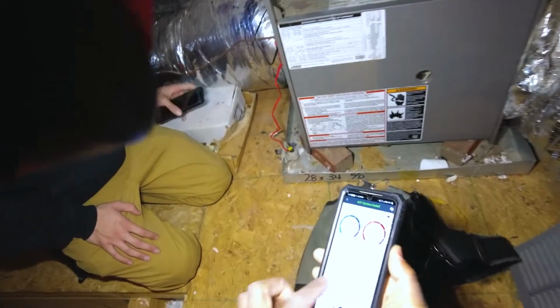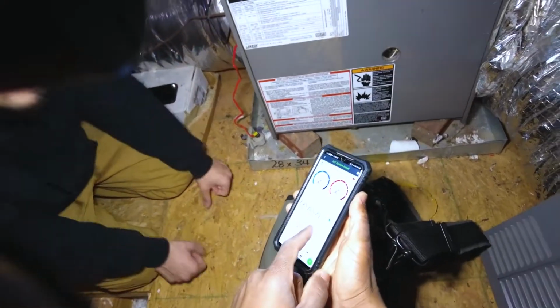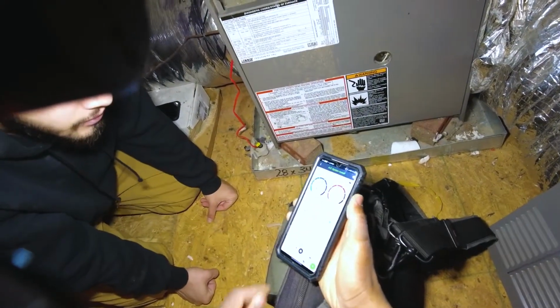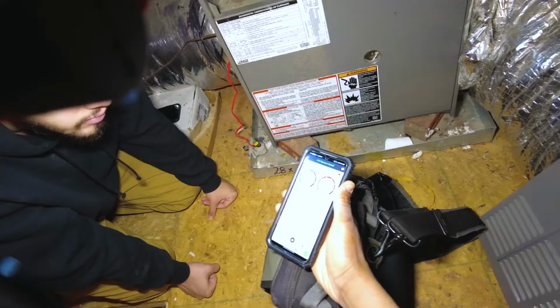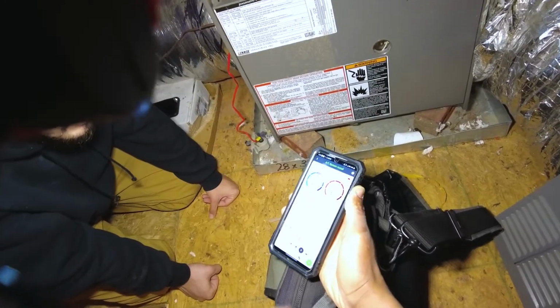And we can see our psychrometers. Got a 21 degree split, which is amazing. That's good to me. You want it to be between probably 18 and 23, 24 degree split, supply air.